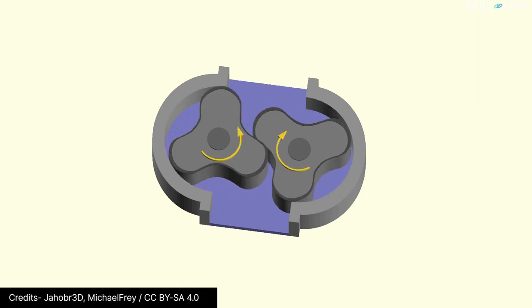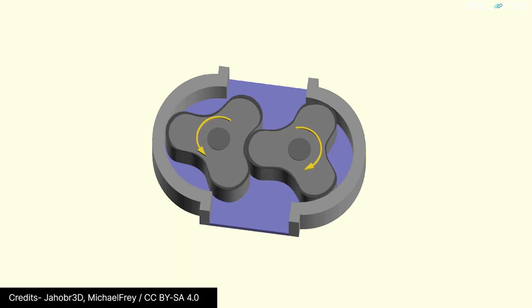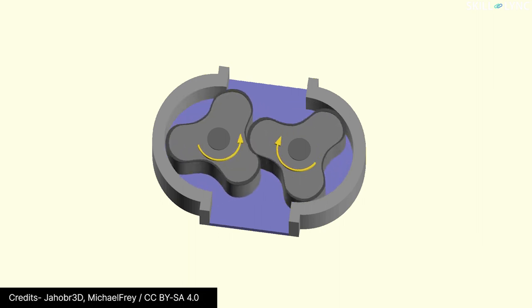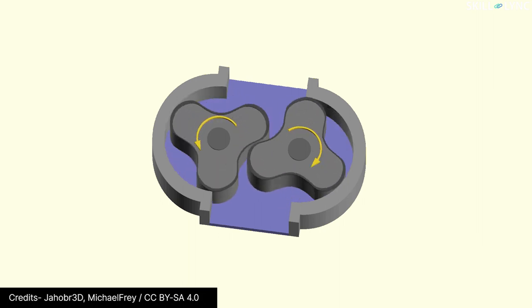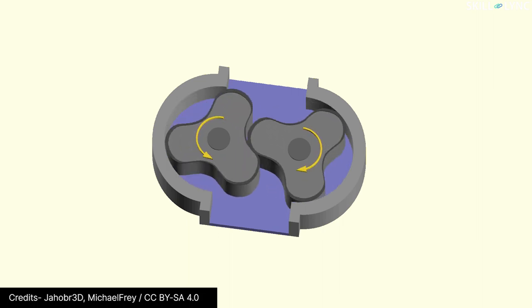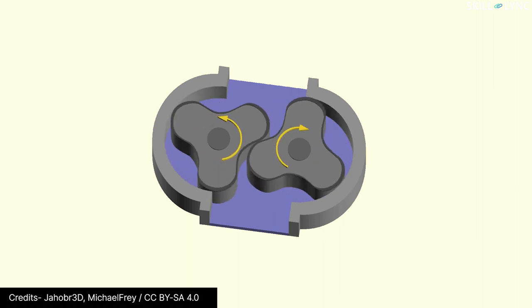When the two lobes of the pumps come out of the mesh, they increase the volume at the inlet side. This forces the fluid into the pump. As the lobes continue rotation, they carry the fluid towards the outlet side. Finally, when the lobes of the pump remesh again, the fluid is pumped into the exit port.